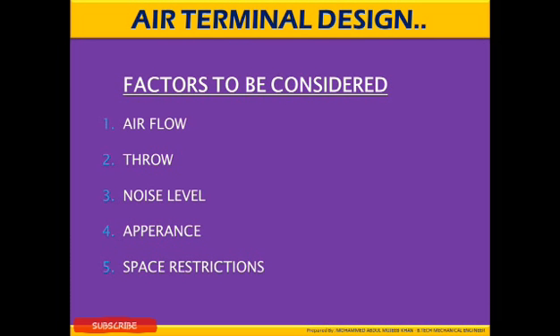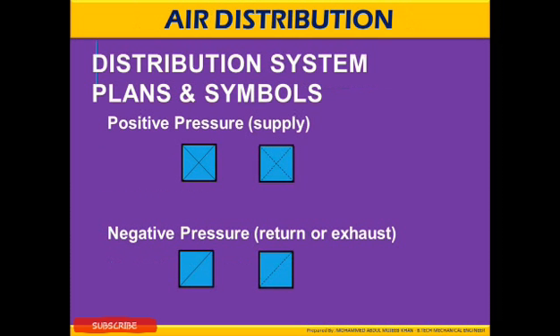Factors to be considered: airflow, throw, noise level, appearance, and space restrictions. Distribution system plans and symbols. Here you are going to see the positive pressure supply, the negative pressure, return or exhaust. These designs are considered in duct designing to identify the types of ducts. This design for the square illustrates the supply air duct, and the negative pressure return or exhaust is drawn in this particular way.